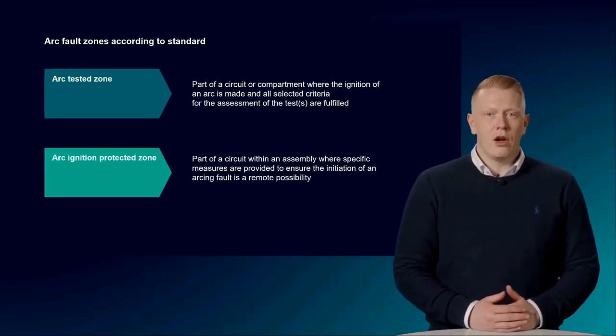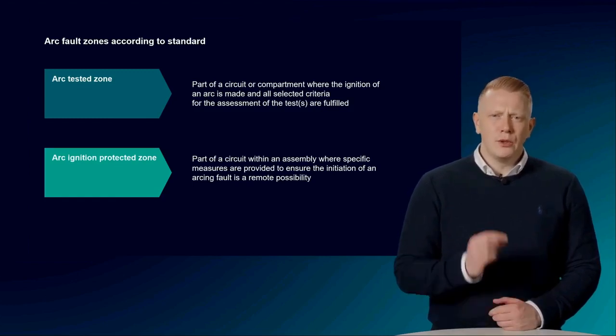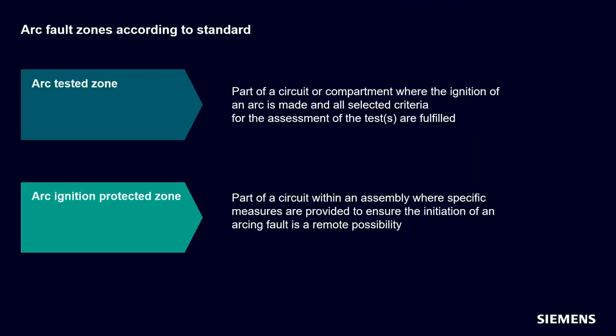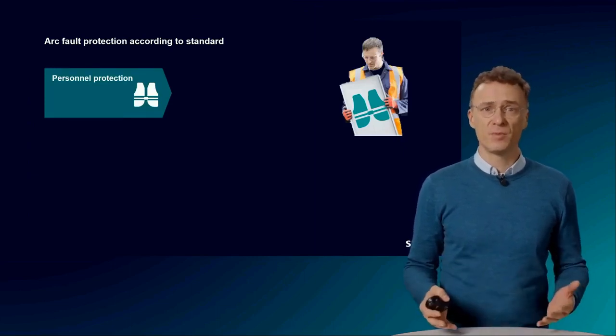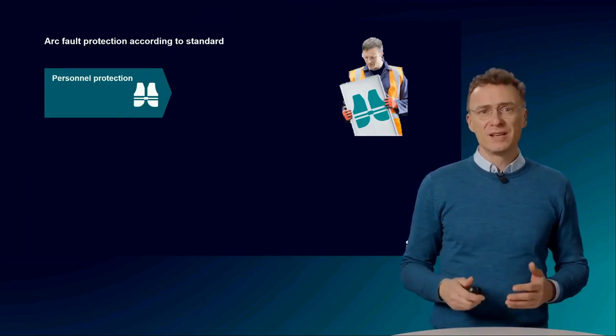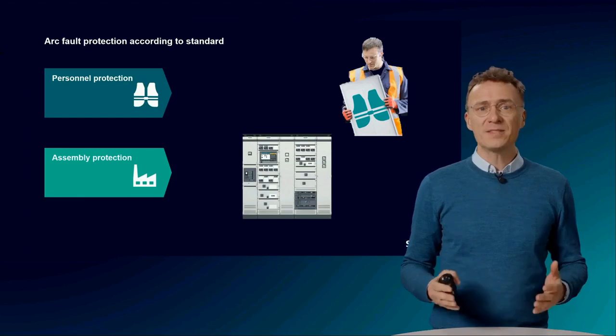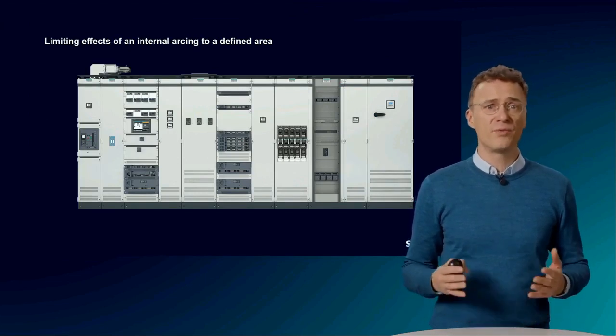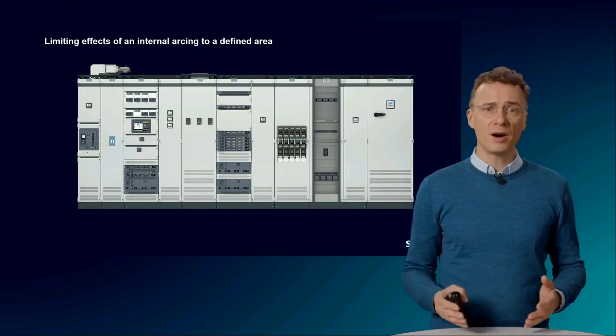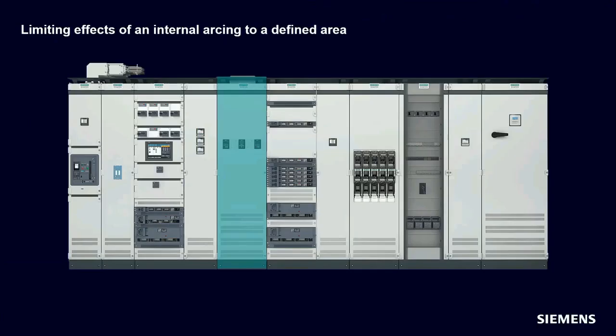It is important to define the protection goals in advance. The minimum requirement is personal protection, meaning a person standing in front of the system will not be harmed. In addition, system protection can also be achieved, which is important for avoiding or reducing downtime. The effects of the arc fault are then limited to a defined part of the system — for example, a cubicle of the switchboard, which would have to be replaced after the event. Or the area can be narrowed down further to one compartment.